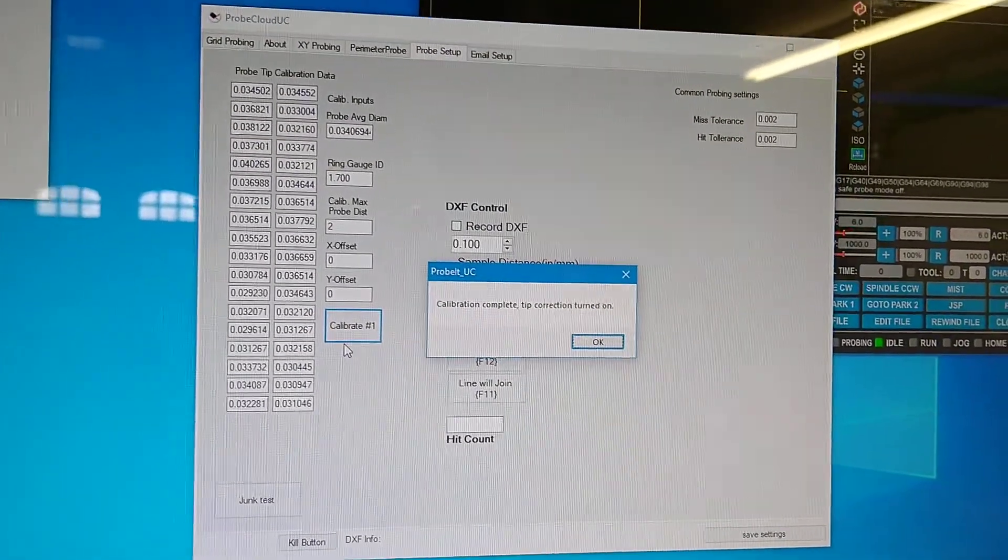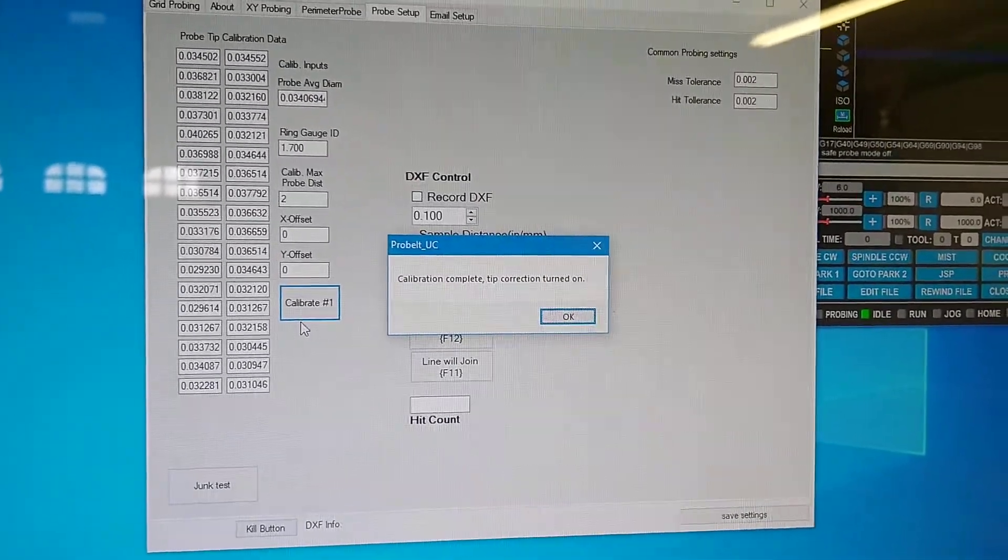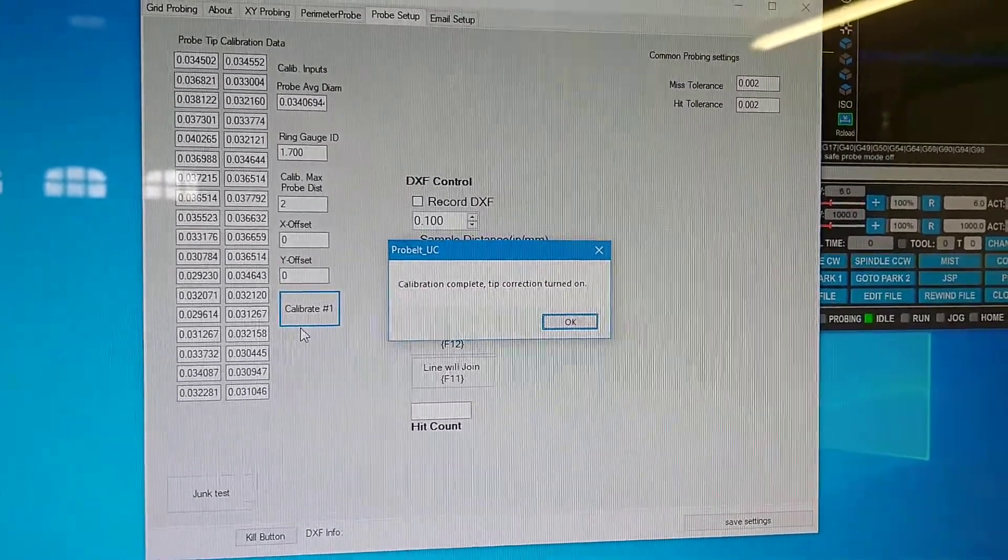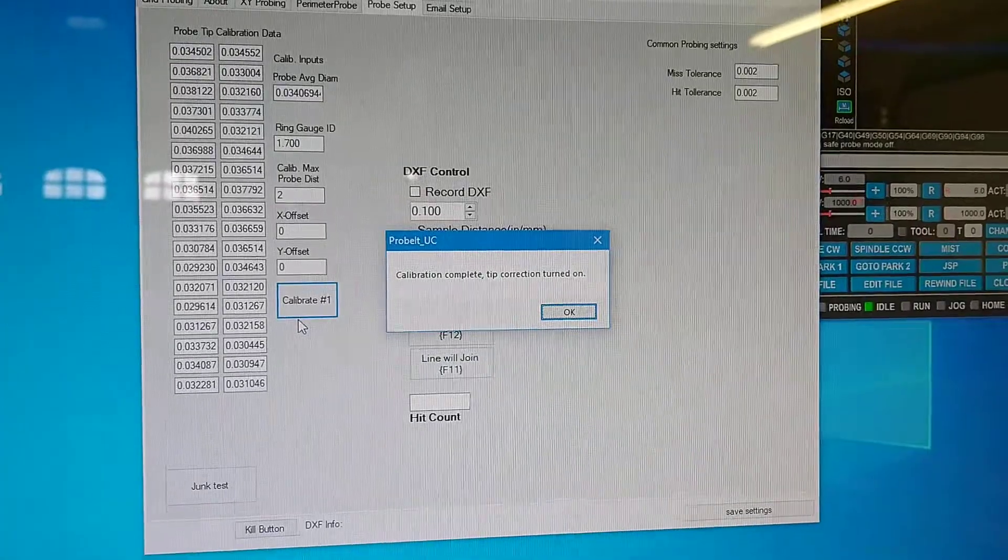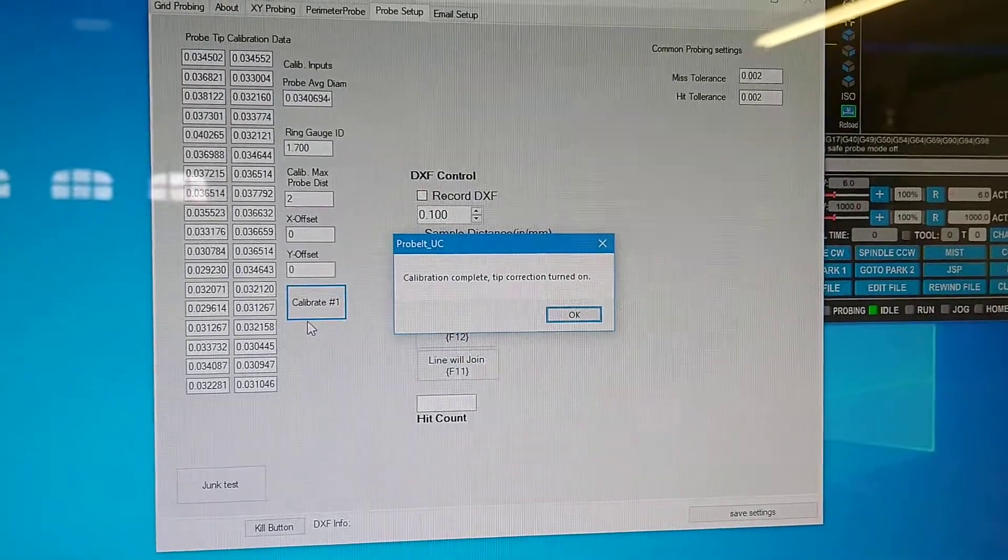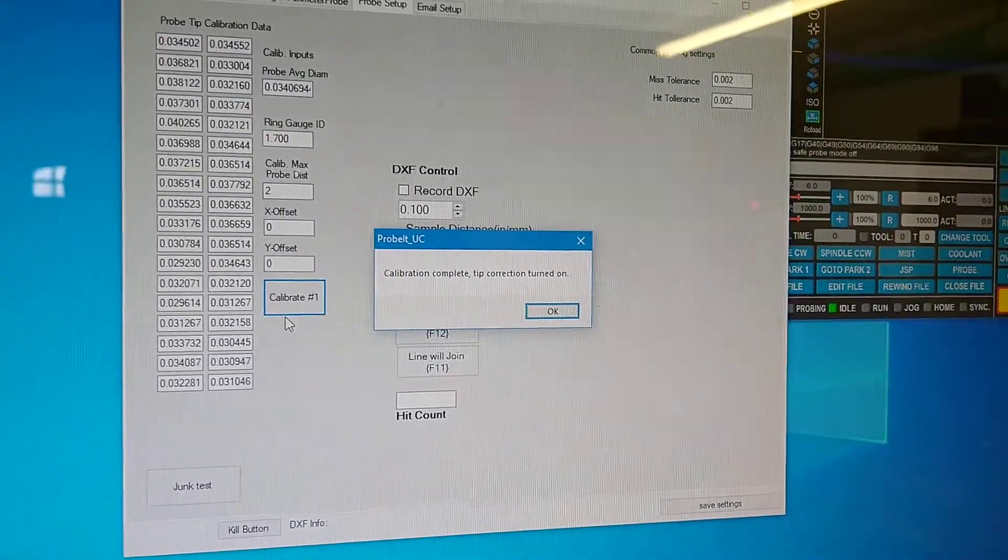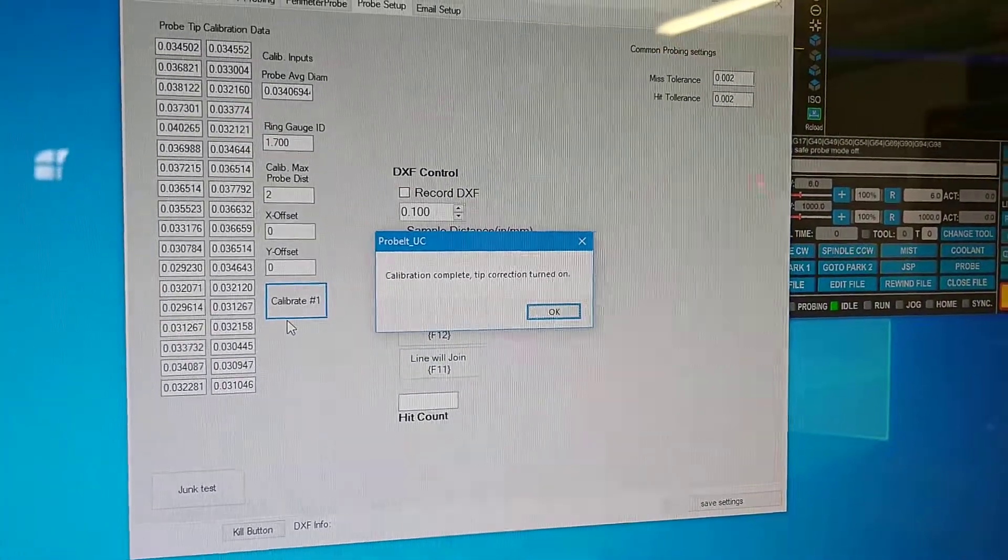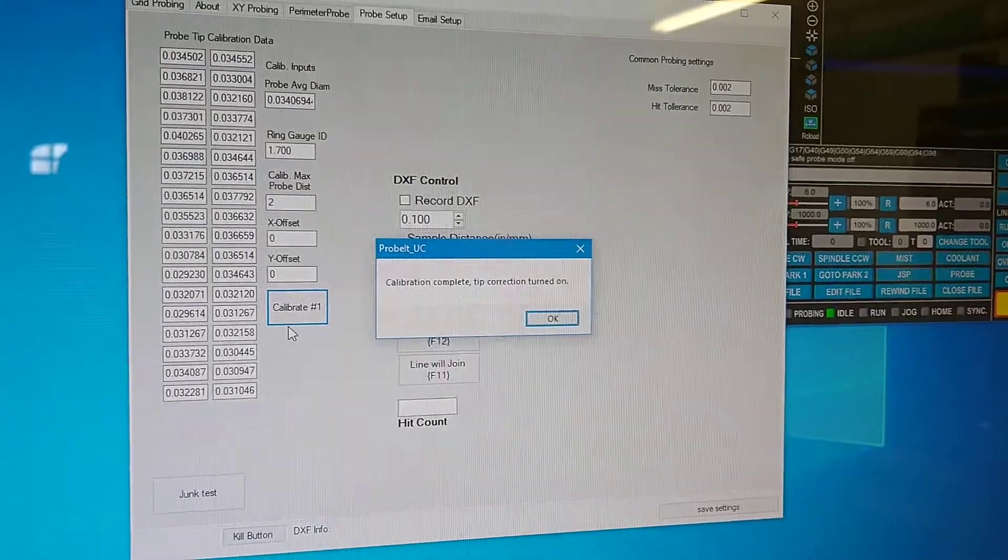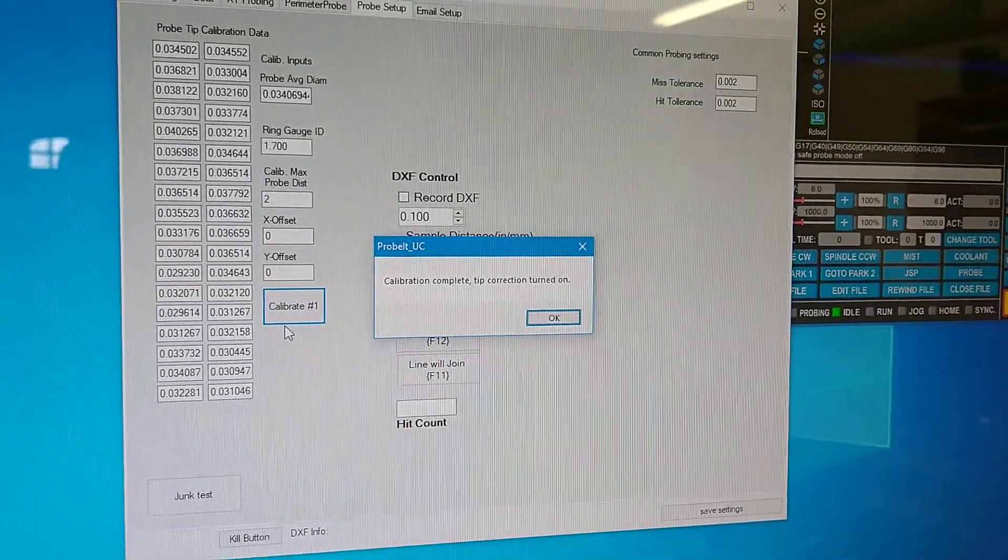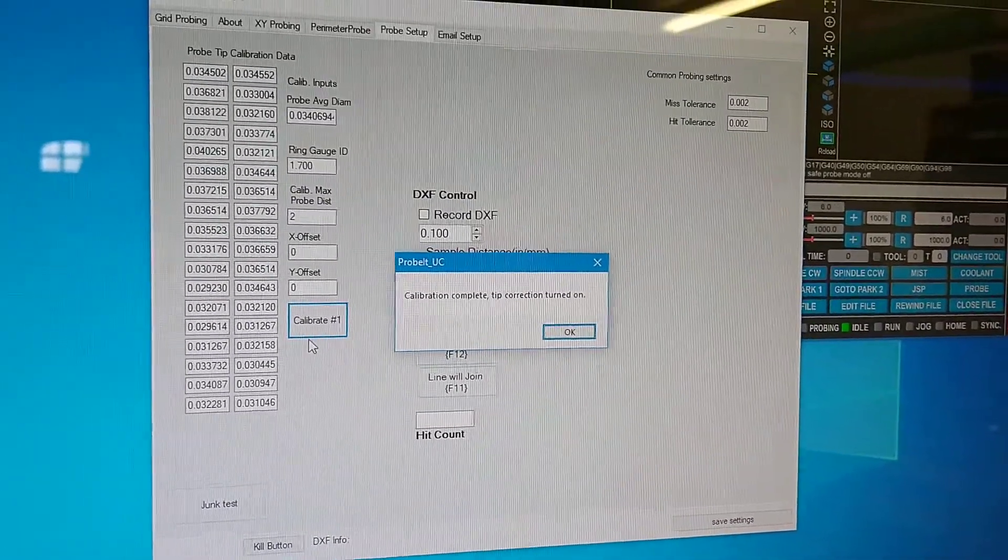And there it's finished filling out the calibration table for all angles in 10 degree increments for a full circle, and that'll be the basis for all probing routines then for all angles and doing perimeter tracing.